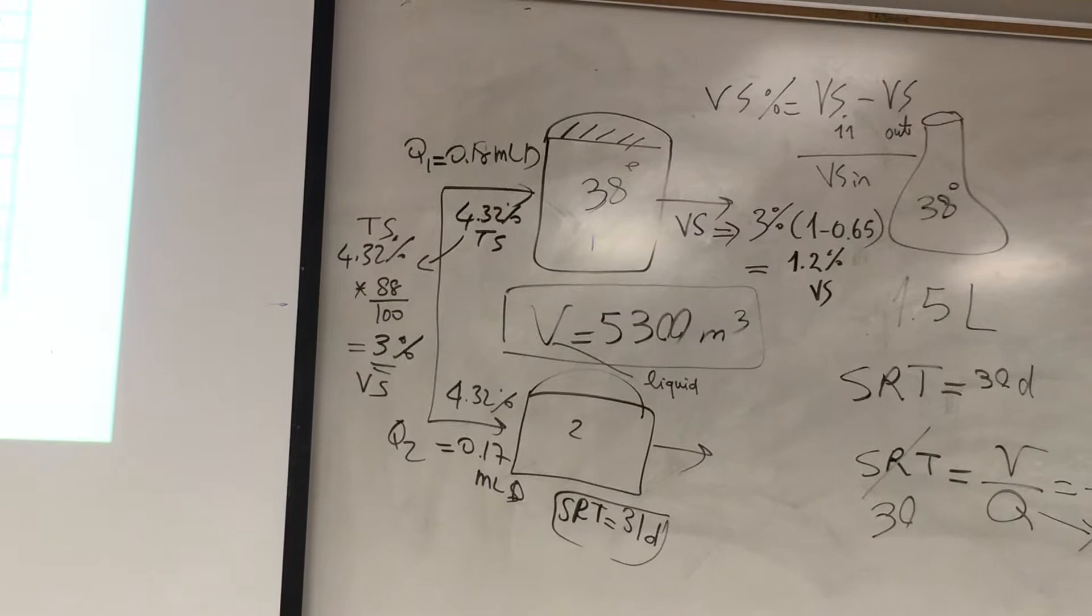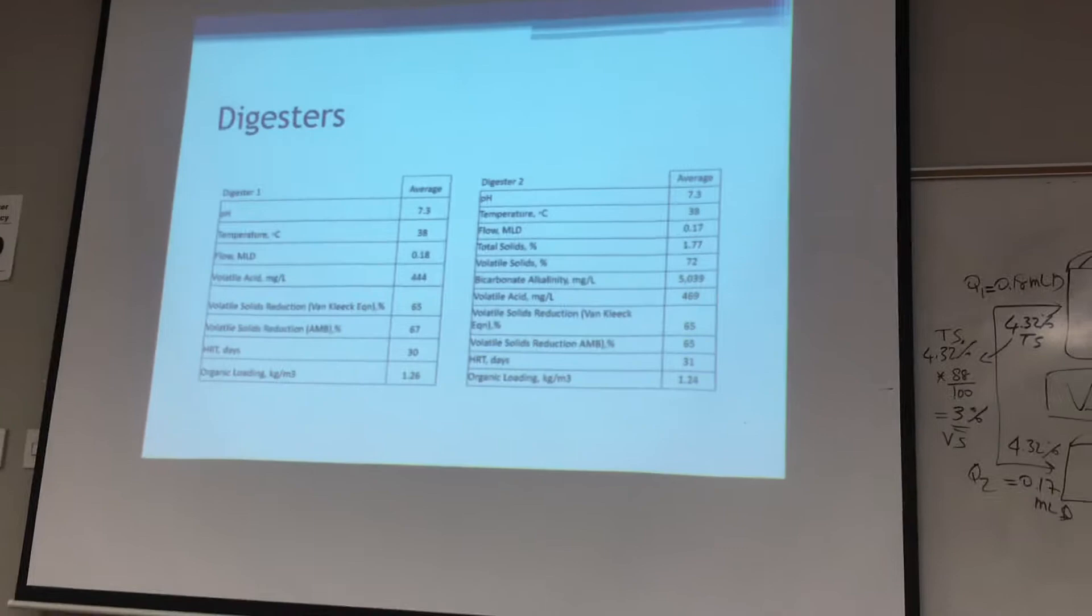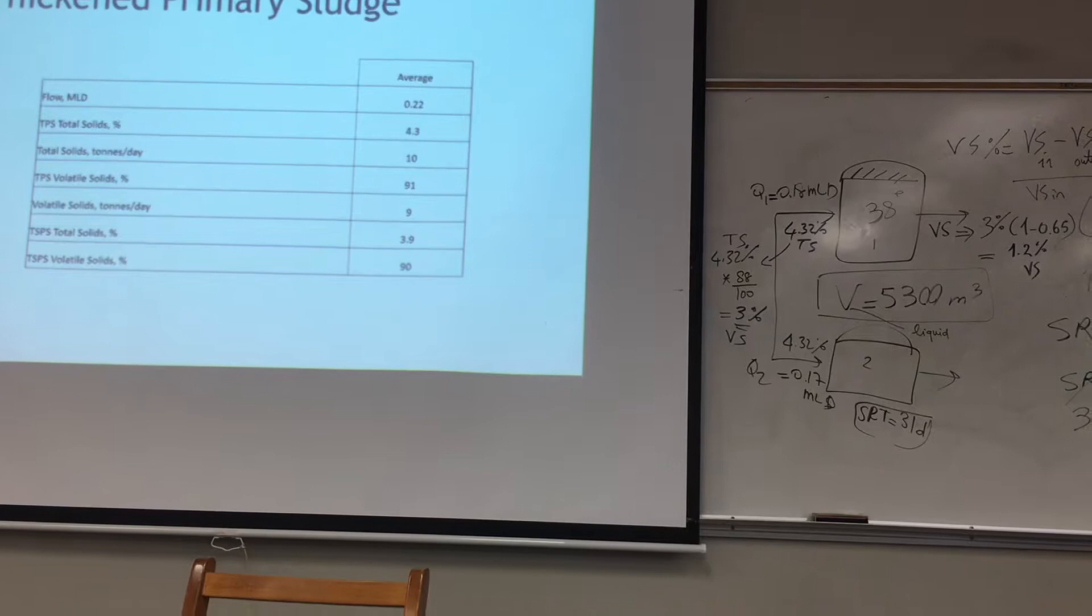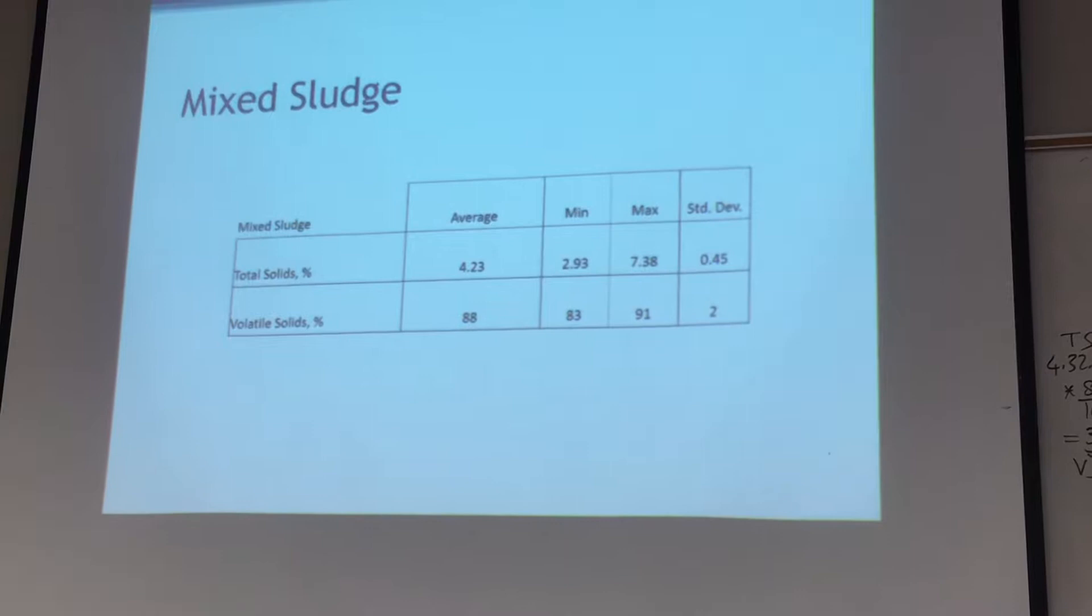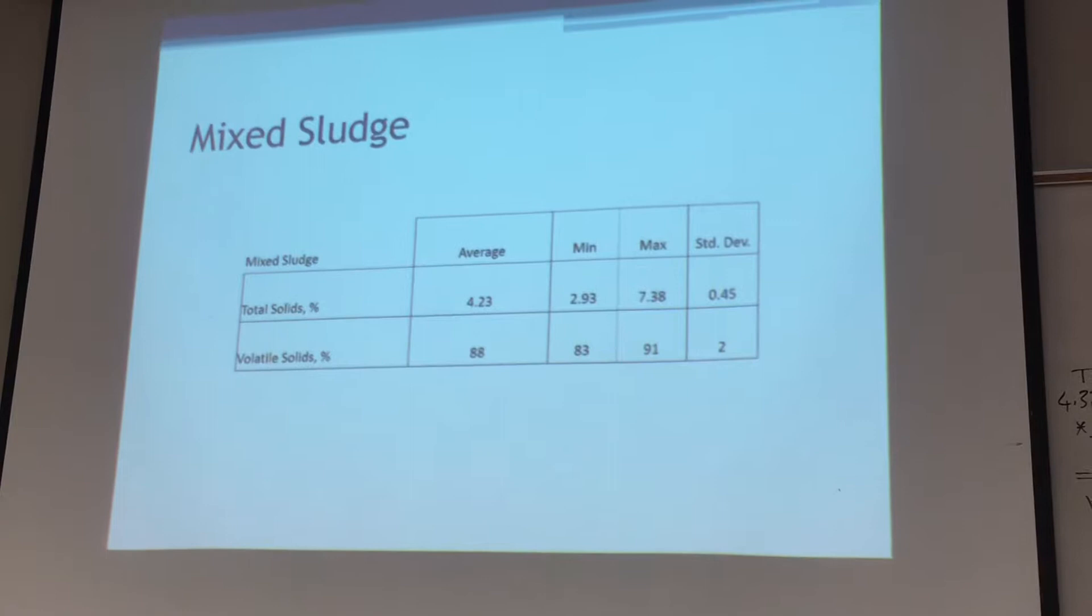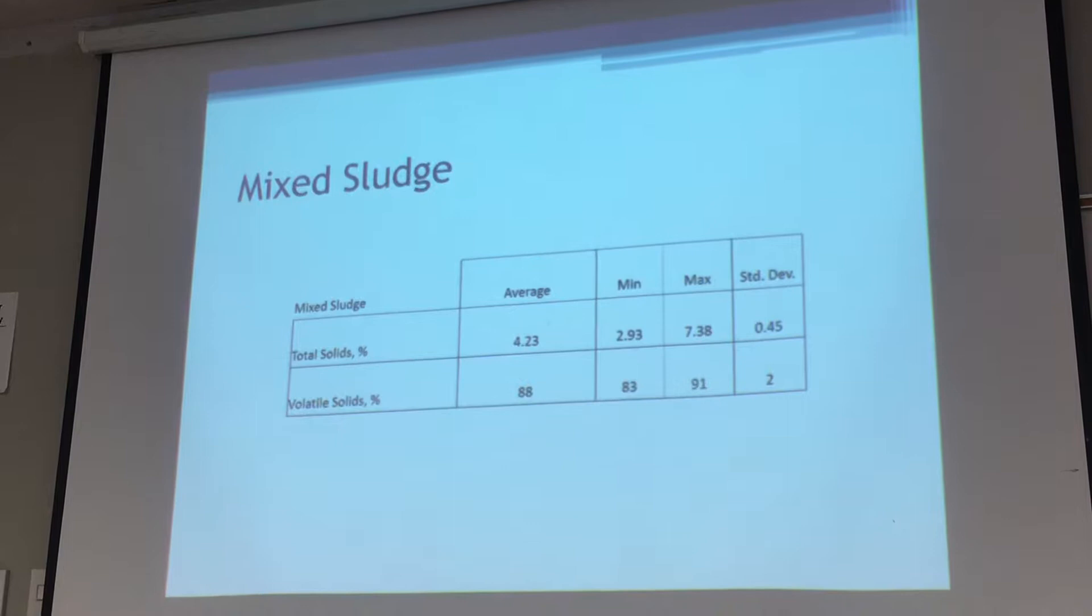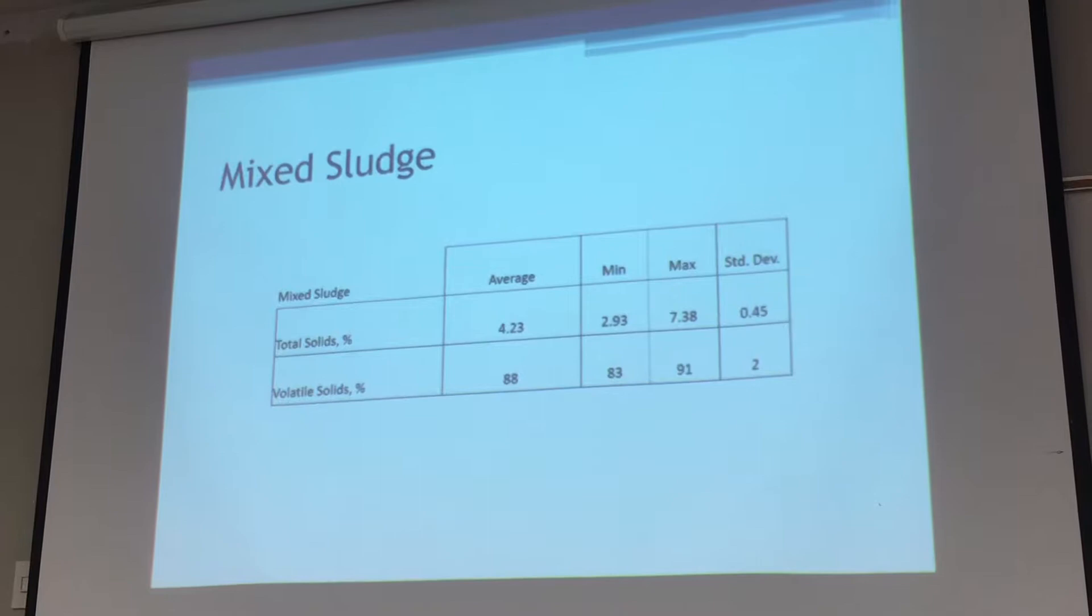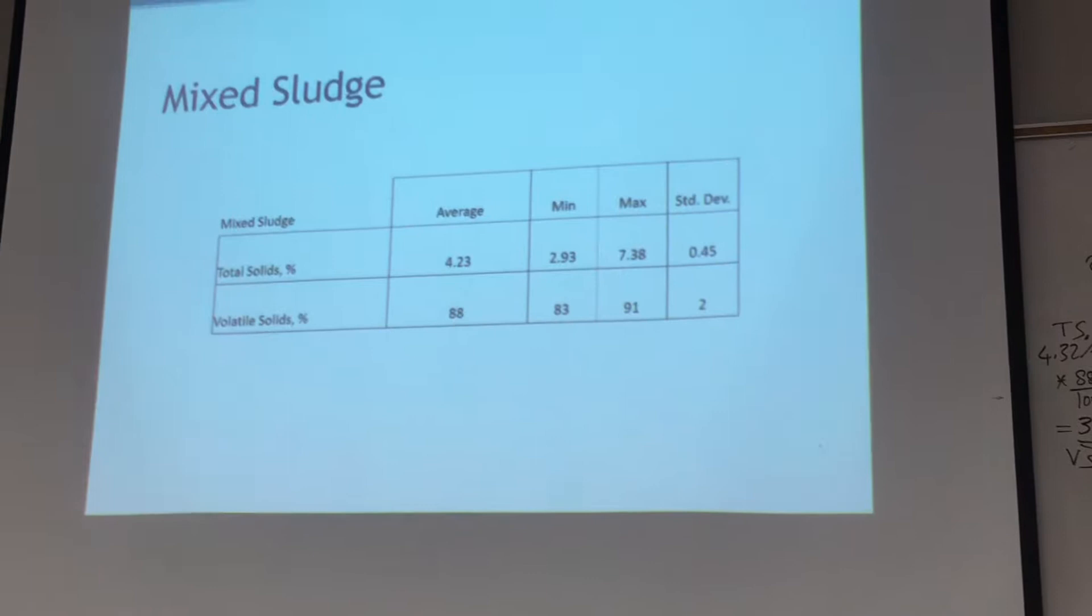Based on what's coming out, they have VS destruction around, so 4.32% times 88%. If this is 3% VS, they have 65% of removal. So VS coming out is basically 35% of this. So probably 1.2% VS. That's your baseline scenario. In order to calculate your VS removal, you go by VS coming in, VS coming out, divided by VS coming in. So that's your removal efficiency.